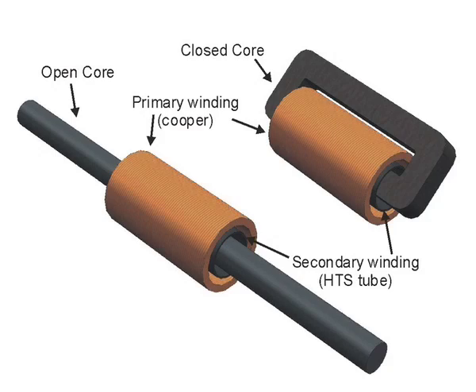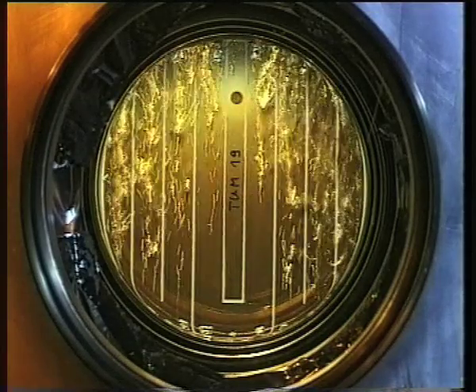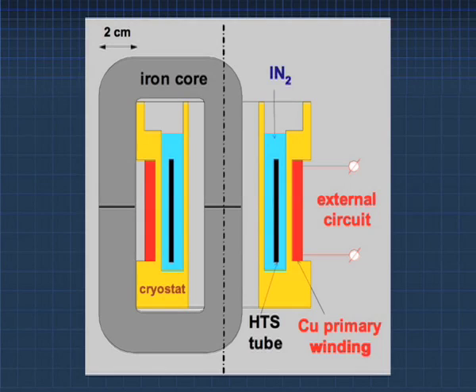The resistive and inductive fault current limiters require much the same characteristics from the material. You can regard the inductive fault current limiter as a one-turn transformer. This essentially puts the single turn in series with the supply, and so it behaves in exactly the same way as the resistive fault current limiter. Because of this transformer action, the superconductor in the inductive limiter has a lot of amps and very few volts, whereas in the resistive one it has fewer amps and lots and lots of volts.